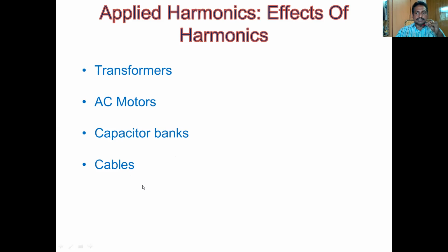Then cables. When the harmonic current flows through the cable, it will heat it more than when the fundamental current is carried by the cable. So that is about the effect of harmonics. Then busways do not function properly when the harmonics are flowing. Then protective devices may malfunction. Relays, circuit breakers, and CTs, PTs are all protective devices. These devices may also be affected.